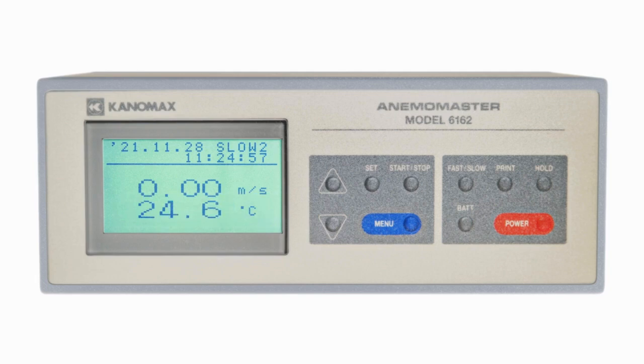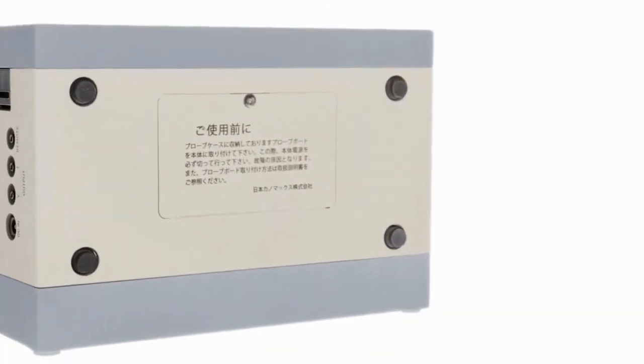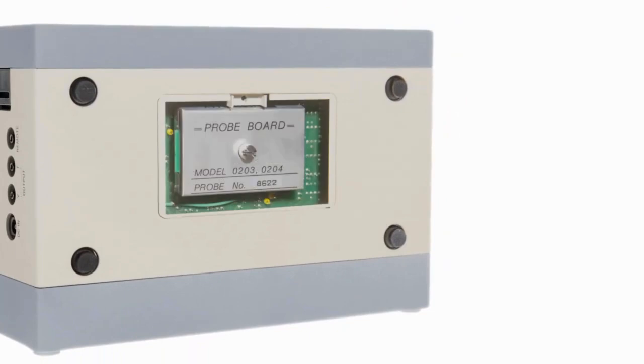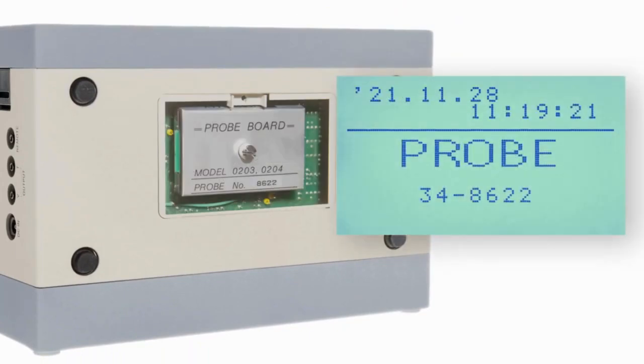To make sure you're getting accurate readings from the start, confirm that the number on the probe cable matches the one on the probe board found on the inner panel beneath the anemometer and the screen shown when you power on the anemometer without a probe connected.